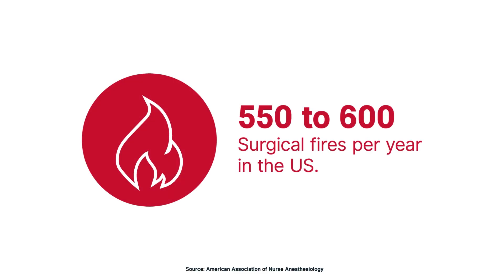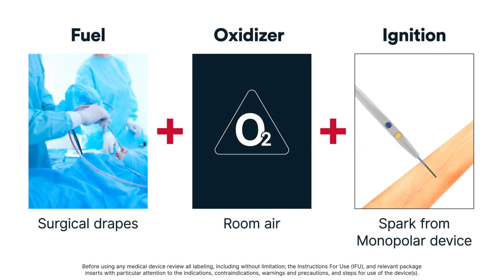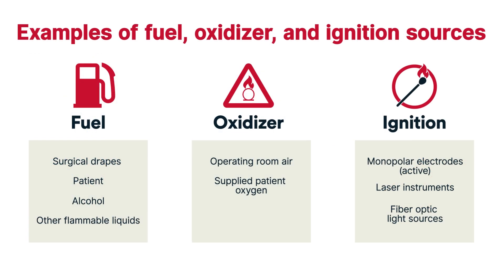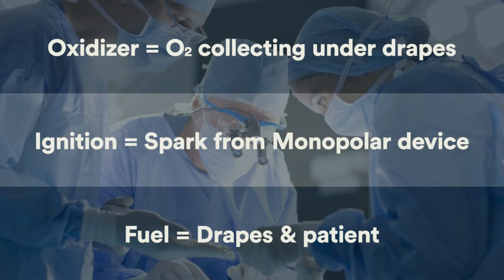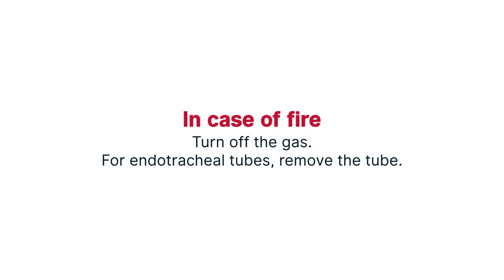Surgical fires are one of the most serious risks in surgery. In monopolar electrosurgery, 550 to 600 surgical fires per year happen in the U.S. Surgical fires require a fuel source, oxidizer, and an ignition source. A spark from an active electrode can ignite a fire in the presence of fuel and an oxidizer; examples of common fuel, oxidizer, and ignition sources in the OR are shown here. One situation where a surgical fire can occur is during a facial or tracheal procedure where the oxygen delivered to the patient accumulates under the surgical drapes, forming a tent filled with oxygen. In this scenario, a spark from an electrosurgery device can ignite the oxygen and set fire to the drapes and the patient. In this event, immediately turn off the gases to eliminate the oxidizer so that the fire can be extinguished. In the case of an endotracheal tube fire, it's critical to immediately remove the tube.